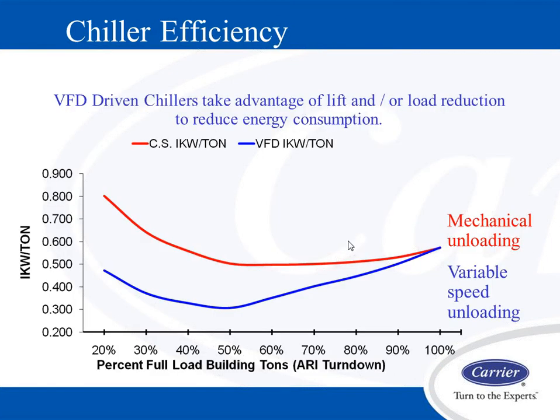When we look at chiller efficiency, here in red is a constant speed centrifugal. In blue is a variable speed centrifugal or screw, you could say. On the bottom we have percent building load, or ARI turn down, and on the left-hand side we have kW per ton. At the full load point, and full load happens very little, my machine is running at 100%, I'm at design conditions, and my building is fully occupied and loaded, operating at design wet bulb temperatures in the tower. At that point we have very similar operating points at the 100% load point between a constant speed machine and a variable speed machine.